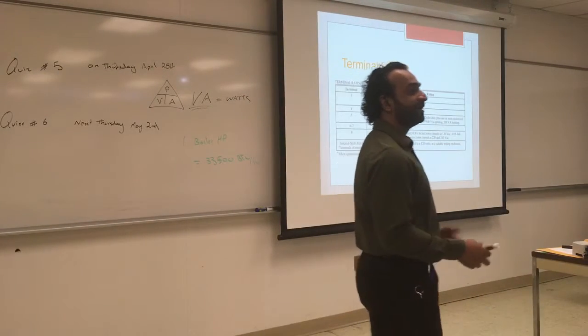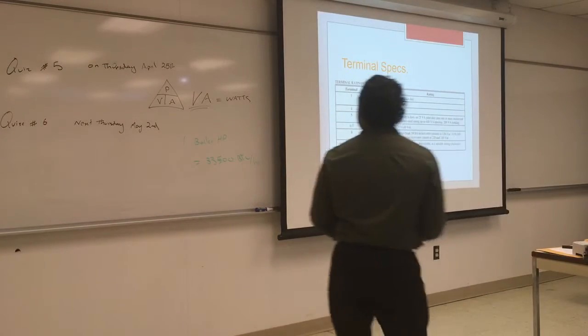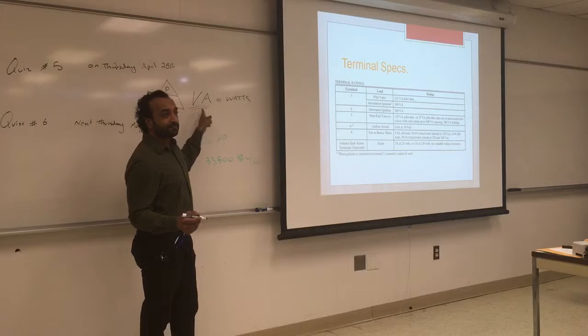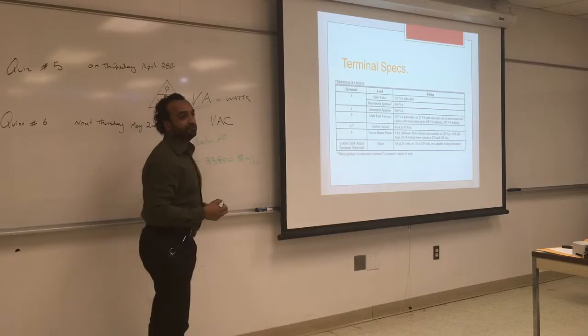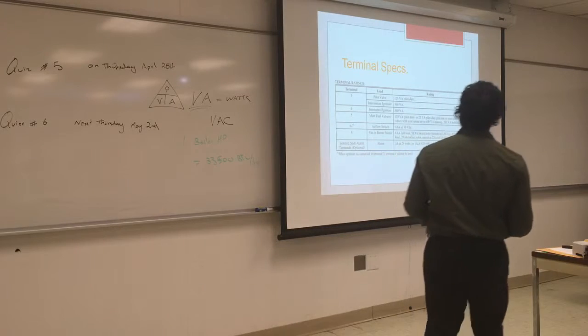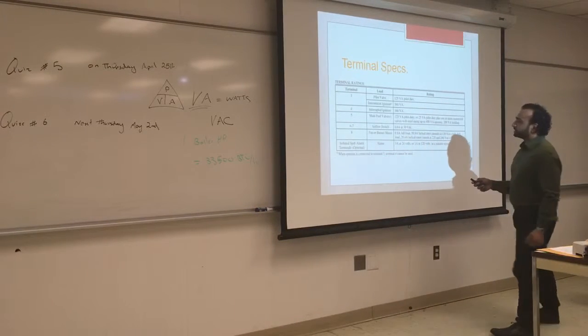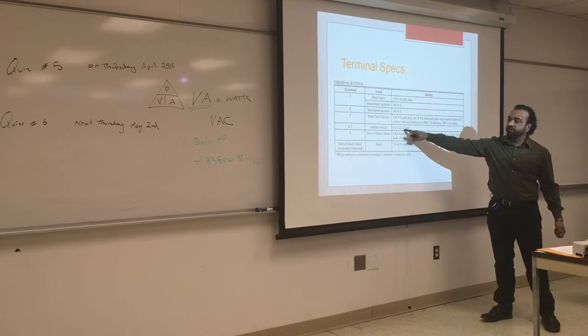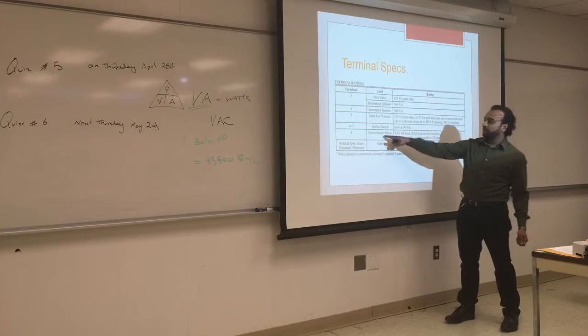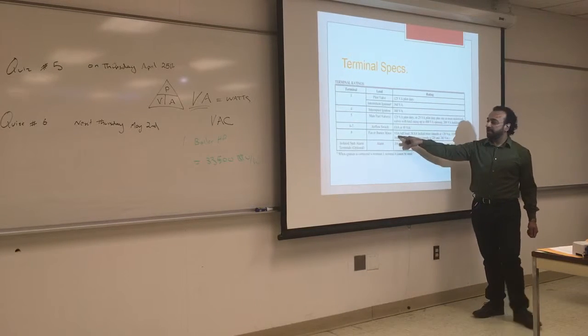Come on guys, it's hard for me to talk while you guys talk. So that's watts. And sometimes you will see this VAC, that's just voltage. So familiarize yourself with those notations. Airflow switch, this is the amperage, and it tells you VDC here, 30 volt DC. I'm just trying to help you decipher how these codes are done. Fan or burner motor, that's going to be 9.8 amps full load and 58 locked rotor.